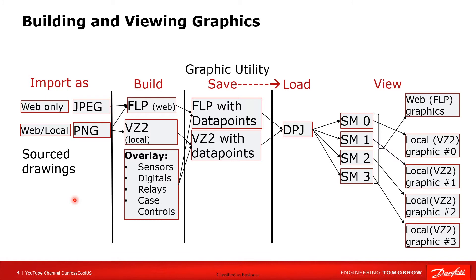This overview shows the whole operation: you have the web drawing, which can be a JPEG or PNG. Once you import it and begin the build process, it becomes an FLP file. You overlay all the data points, do a save, and the save transmits everything to the control. That creates the DPJ file — the FLP and the data points are now combined into a project file and sent down to the control.